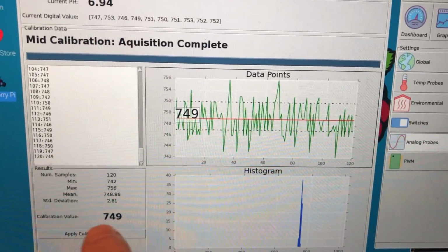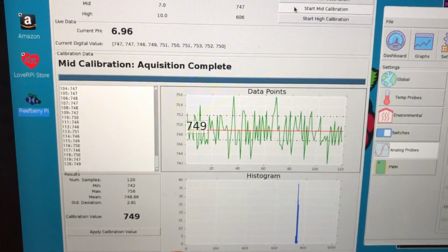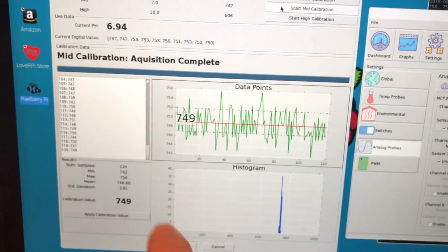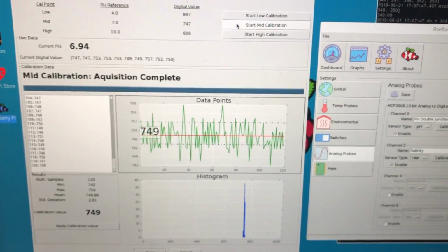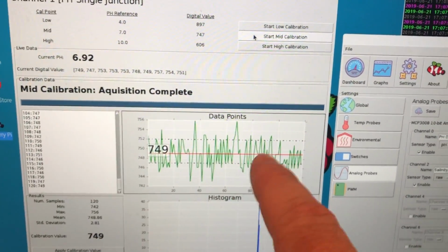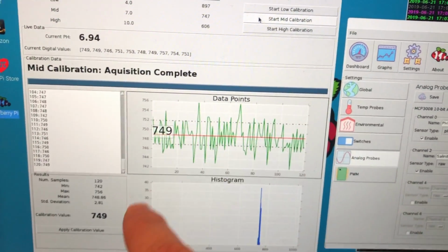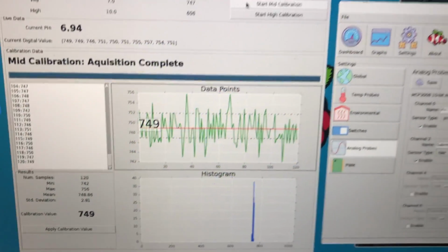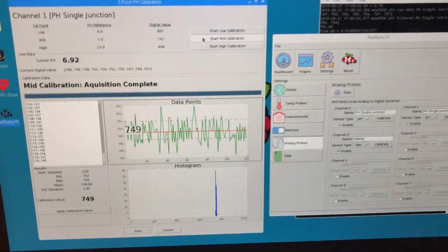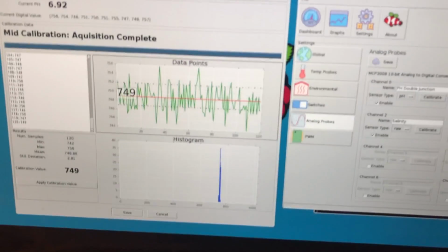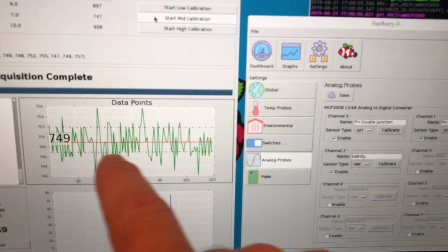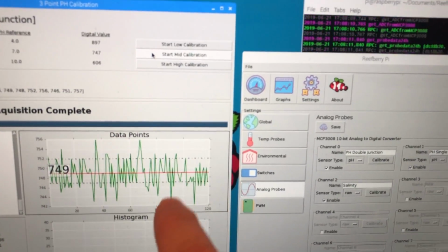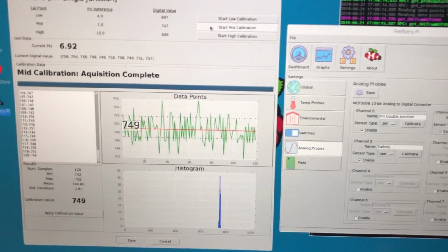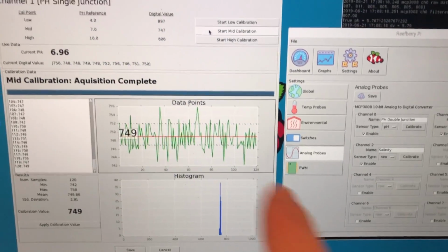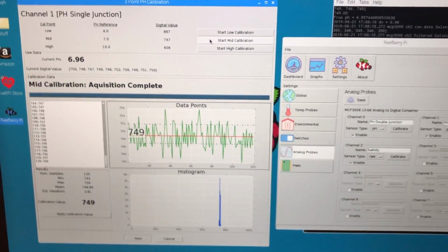Just some stats there. The important thing, obviously, is the calibration value in the end. Then the standard deviation. If you know anything about statistics, it's basically a gauge of how good my data is. My data points were falling within a standard deviation of 2.81, which is pretty good. I've noticed if I'm getting good data, it's usually under a standard deviation of 3. And then I calculate those lines and plot them on here. Anything that falls outside of that range I consider outliers, and I am not including them in my data set when I do my final calculation for my calibration point.